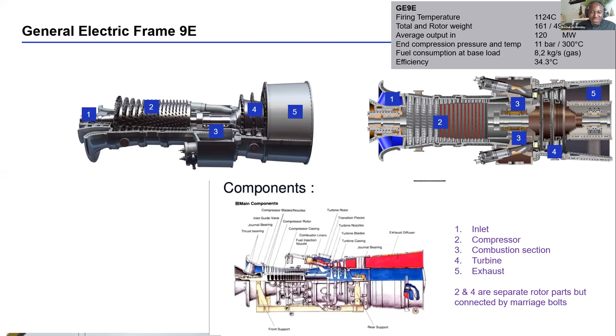I've explained the exhaust. Then you have the GE gas turbine. Also, there are two rotors connected together. So this is one rotor that has the gas turbine, the turbines, and this is another rotor with the compressor. So during maintenance, you can decide to lift these two rotors as a body. That means you need a bigger crane. But if you don't have the opportunity, there's an opportunity in this coupling here to disassemble it and take the rotors piece by piece. So this is one advantage you have with this GE, which some other ones don't have. So normally this is if you leave the rotor together as one.